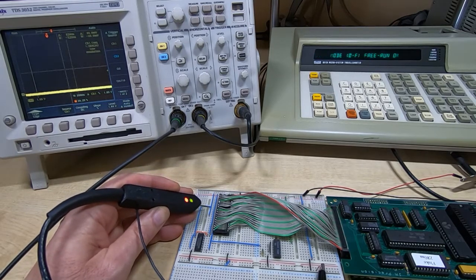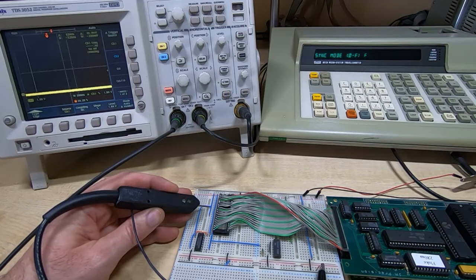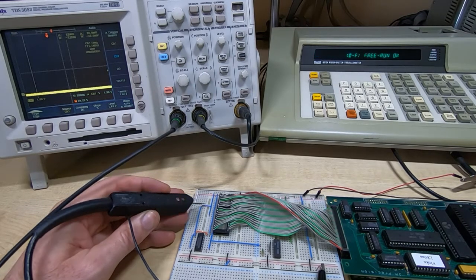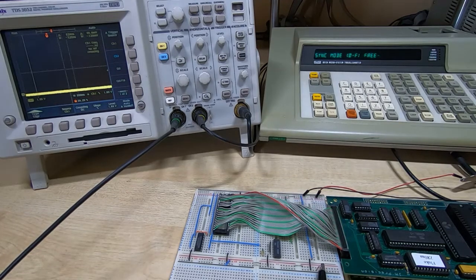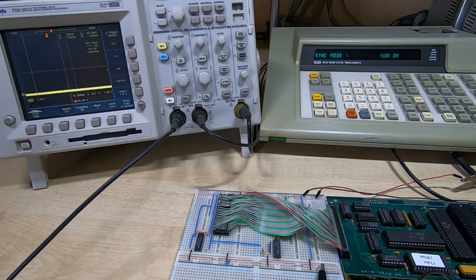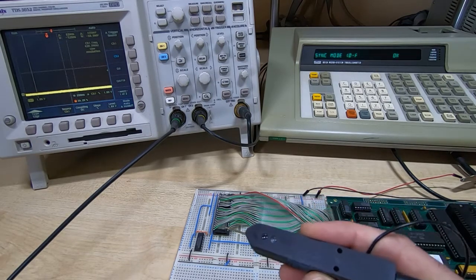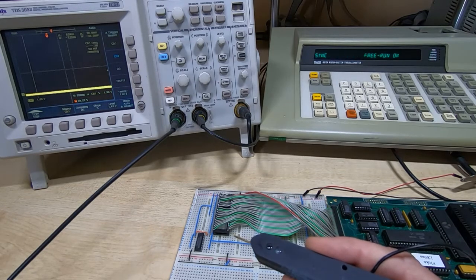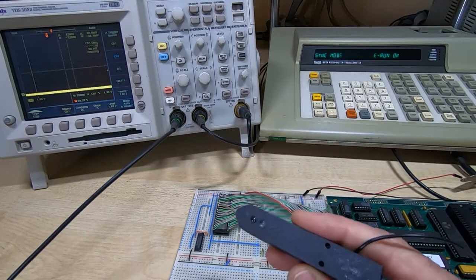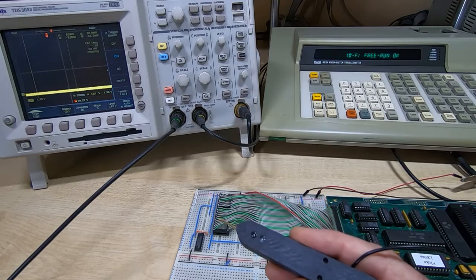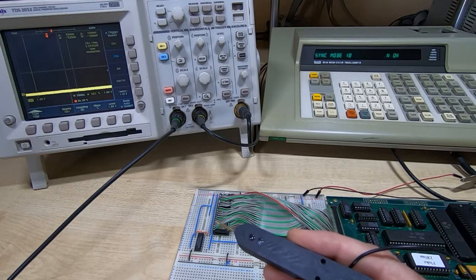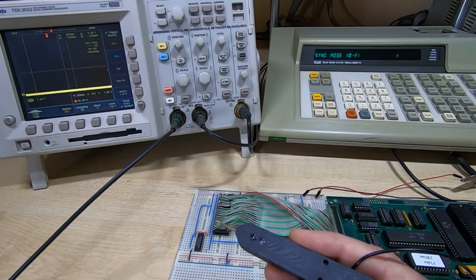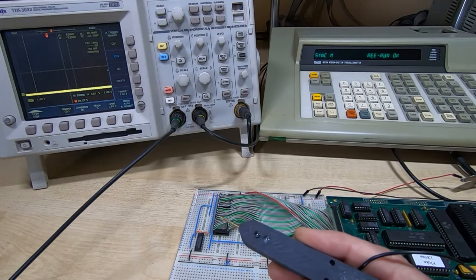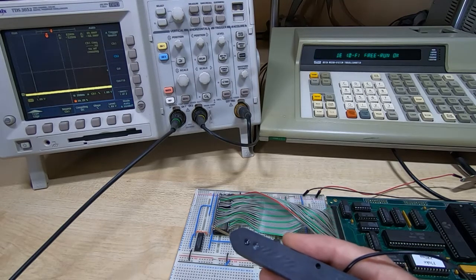camera. So we're now getting the red and the green pulsing, and that means that we are getting a signal that's going below the low threshold and above the high threshold. By default, the setup on these probes is that the high threshold is around 2.4 volts, so anything above that will turn the red LED on, and the low threshold is about 0.8 volts, so anything below that will turn the green LED on. The pulses, or the indications, are stretched to a minimum of about 250 milliseconds.